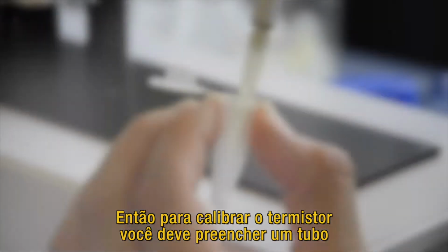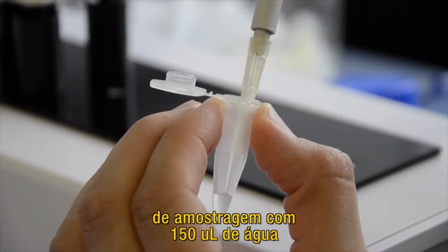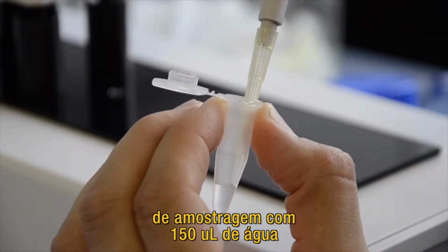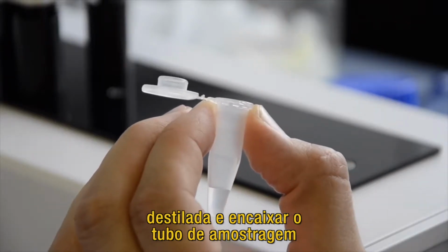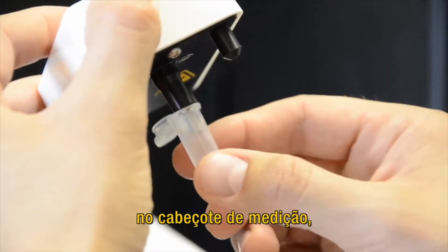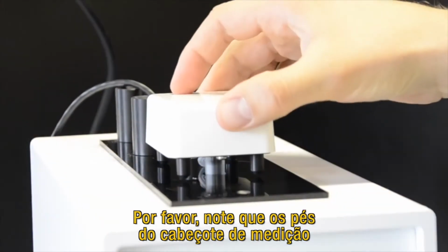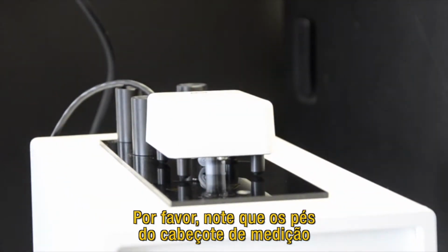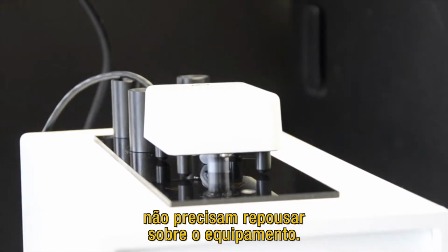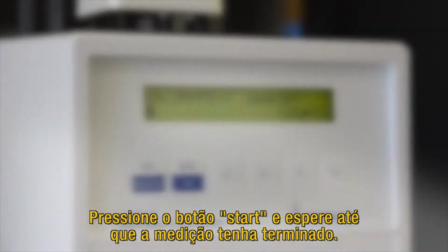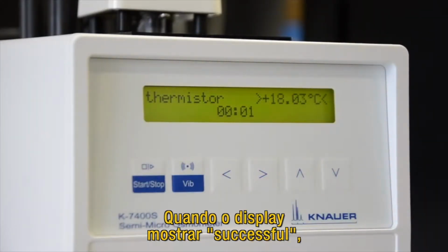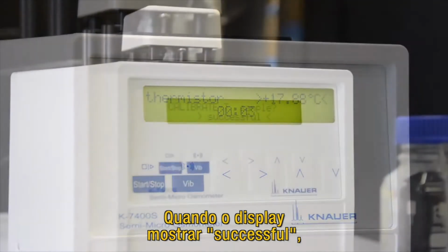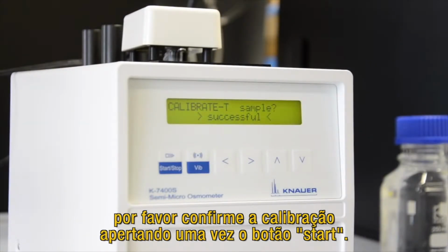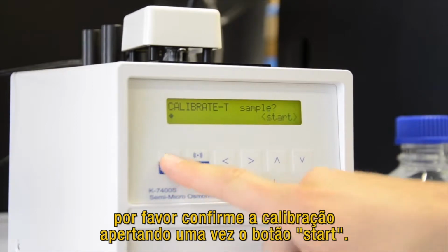So to calibrate the thermistor, you have to fill a sample tube with 150 microliter of distilled water. Then plug the sample tube on the measuring head and place it into the cooling cavity. Please note that the feet of the measuring head do not have to rest on the device. Press the start button and wait until the measurement is finished. When the display shows that the calibration was successful, please confirm the calibration by pressing once the start button.